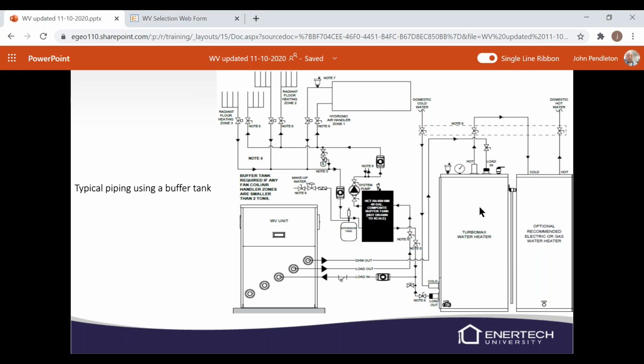We found that out. So we do recommend that you install a backup water heater, and that can be electric or gas. We don't really care at that point. But it's kind of similar to how we did it if you've done the superheater piping on a standard unit and you put in a gas water heater, we would have kind of like a preheat tank. That's kind of what we're going to do here. We're going to preheat the water in the TurboMax and send it over to your electric or gas water heater. And then if it needs to be heated further or the TurboMax is not operating, then we would still be able to supply hot water to the home in that situation. So I would recommend installing a backup water heater as well for if the unit does go down.